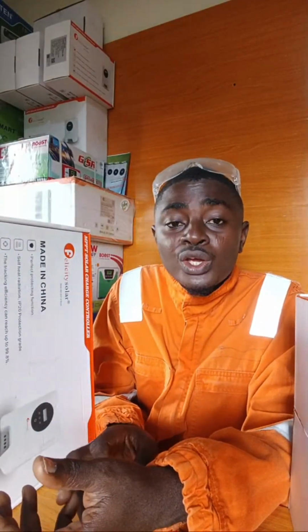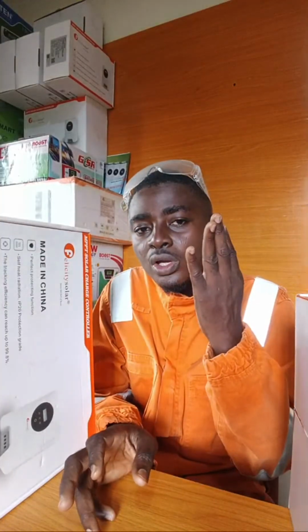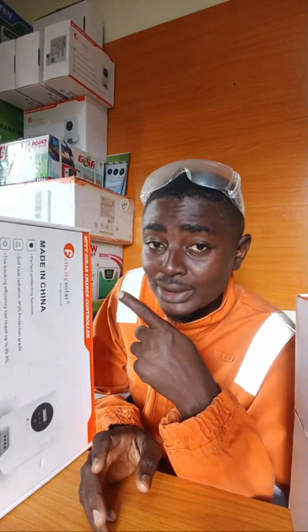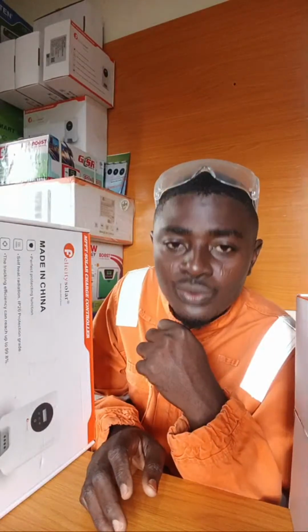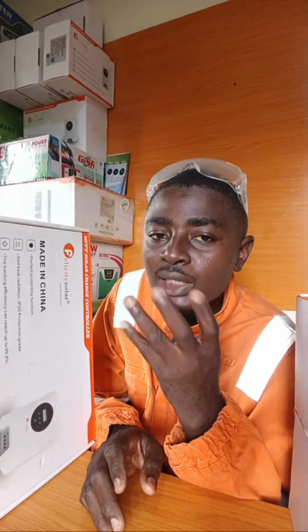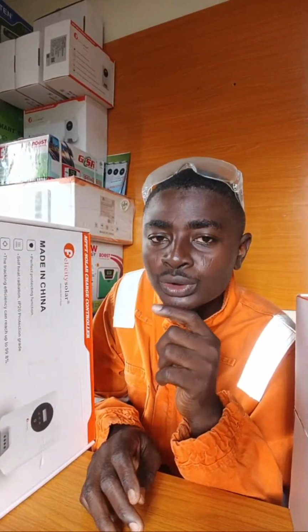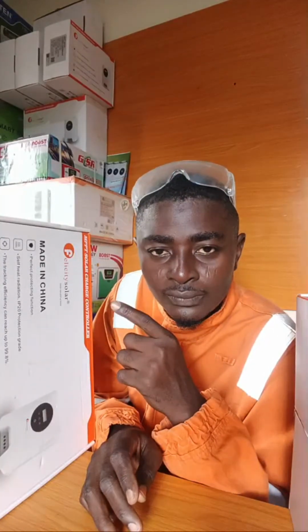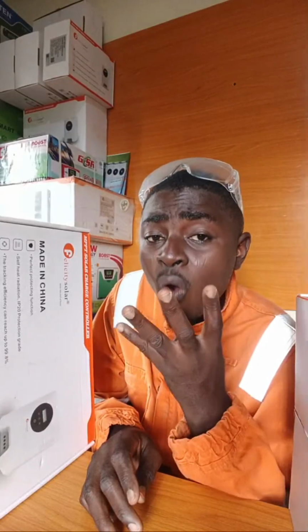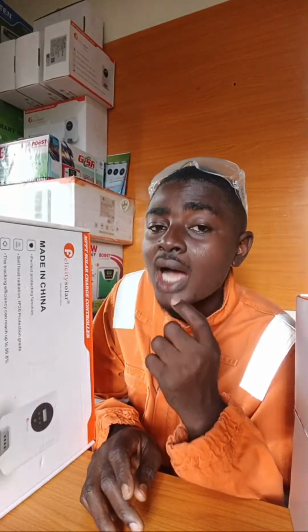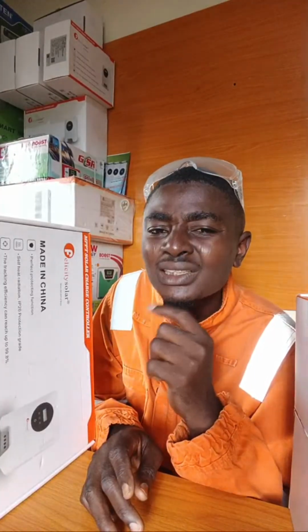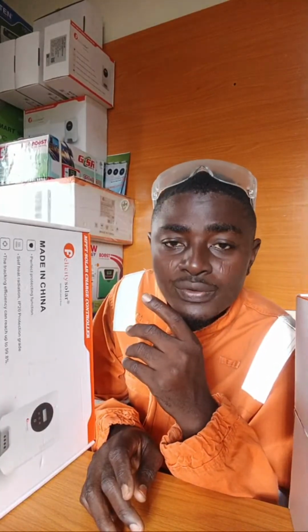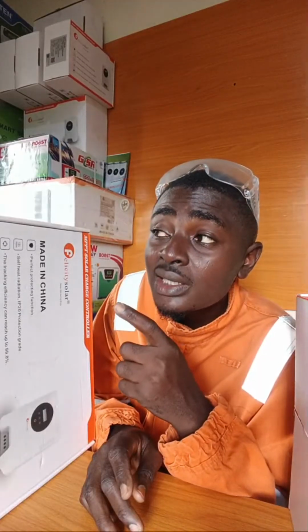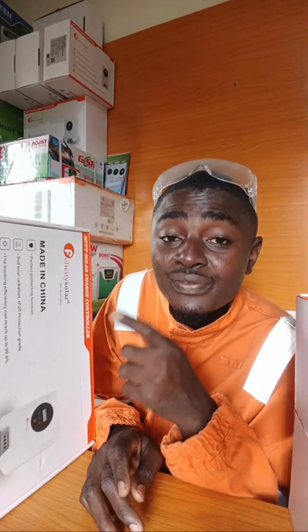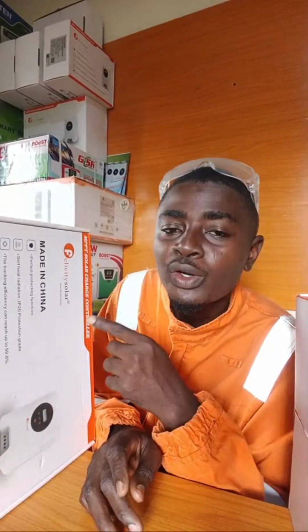The VDC of each panel is 40. So if we connect 4 in series, you'll get the right value. There are 12 panels, and 4 times 3 is 12. So you're going to connect 4 as one string, 4 as another, and 4 as another, to match up all 12 solar panels.